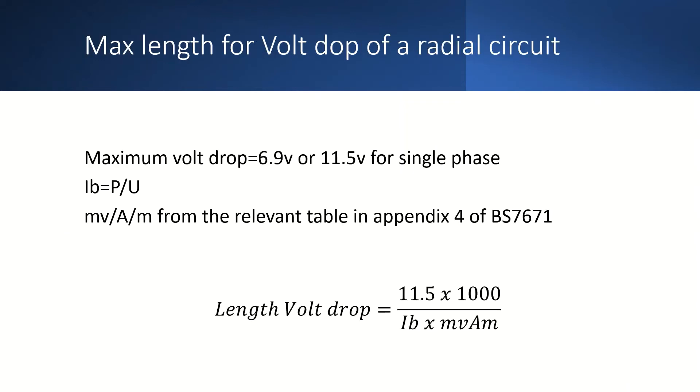So for a radial circuit where we know the loaded watts we can calculate the design current for the circuit and we can find the value for millivolts per ampere per meter in appendix 4 of BS7671 on the table for the relevant type of cable.